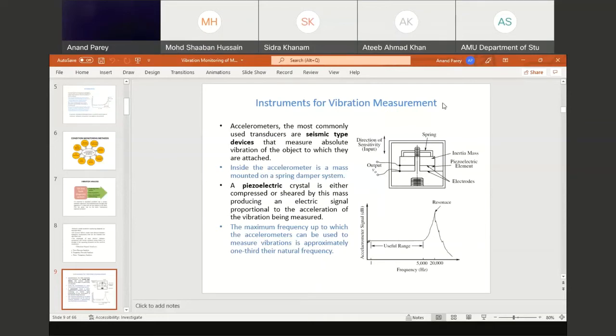Then you will find that for a given frequency range, the response is flat. Whatever is the natural frequency of this single degree of freedom system, you can calculate using the stiffness and the mass, which is under root k by m. That gives you the natural frequency of the accelerometer. Once you know that natural frequency, one third of that will give you the flat response range. This is important because if you measure any frequency greater than one third of the natural frequency of the accelerometer, there will be amplification.